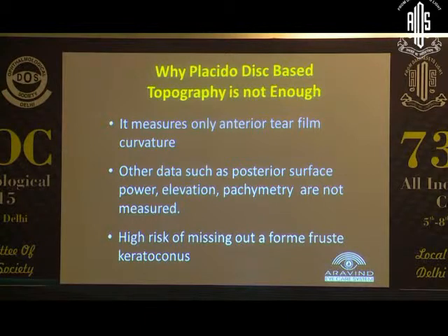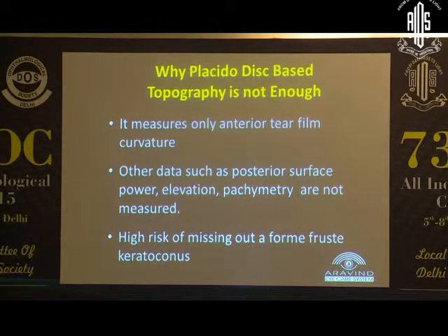So why was there a need for this type of topography? Why was the Placido disk not enough? Because the Placido disk only measures the anterior tear film curvature. Other data such as posterior surface power, posterior surface elevation, and pachymetry are not measured, and there is a high risk of missing out forme fruste keratoconus or subclinical keratoconus.